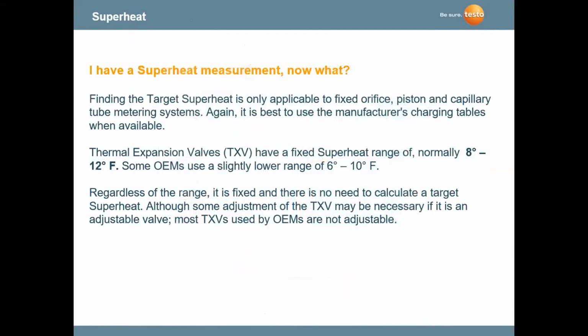Very quick, very fast. So when you get your superheat, whether you're using an analog or digital gauge, you still need to have a targeted superheat. And thermal expansion valves have a fixed superheat roughly between 8 to 12 degrees Fahrenheit. Some OEMs are usually slightly lower, but check with the manufacturer.